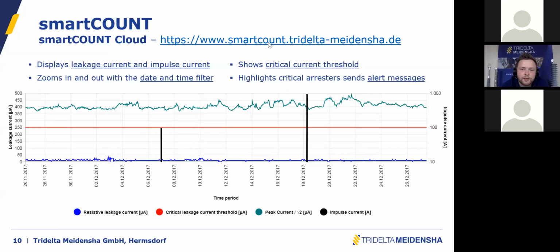Then we have this red line. This red line we give for Tridelta surge arresters. We call it the critical leakage current threshold. It is related to the resistive leakage current. So once your resistive leakage current exceeds this line, the smartCOUNT cloud will decide by its own and send you an email with an alert, and will tell you, okay, this surge arrester on position 1 or 2 has maybe a problem. Please check and decide on your own what to do.